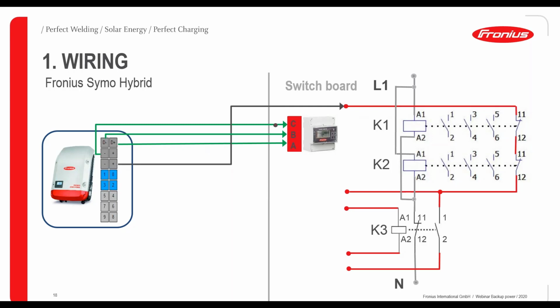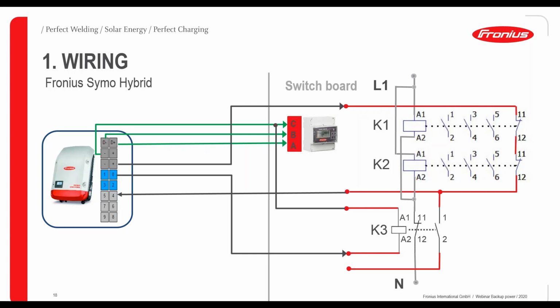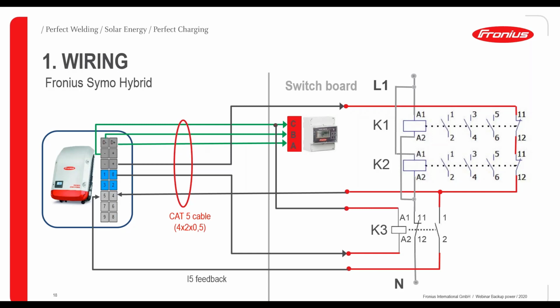Basically, we need 12 volts here on the feedback loop of the contactors K1 and K2. They're going back to I4. Yeah? So we know here the information of the status of K1 and K2. And then we supply K3 from IO0 with 12 volts. And the 12 volt and the ground connection is coming from the pin C on the smart meter, which is the minus pole on the connector of the Symo Hybrid inverter. And then we get another feedback from I5 from the K3 relay, which goes to I5, the feedback here.